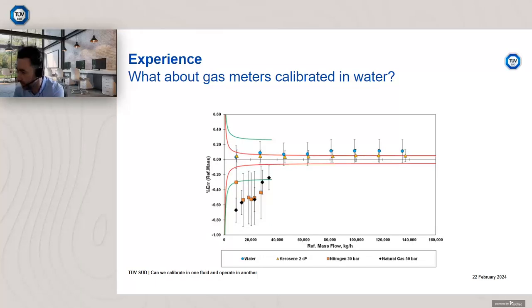So we have nitrogen here at NEL, we operated up to 30 bar, and we also have natural gas data that was supplied from an external laboratory for this device. Now there's various things to be aware of here. There's potential pressure effects for Coriolis meters, and there's also the effect of the flow range that you're operating across. Plus, also consider the increased uncertainty for gas. So the uncertainty for gas here is in the region of 0.35, 0.25%, depending which facility was used. And you can see that if you actually look at the uncertainty bars, they are potentially within the gas specification, although those data points look as if they're slightly out.